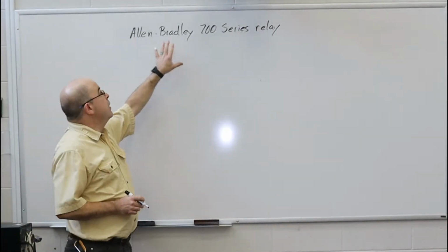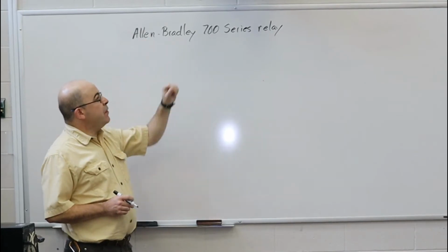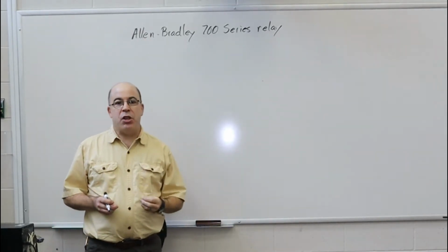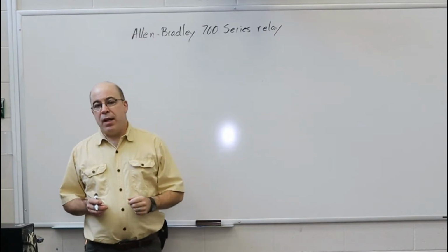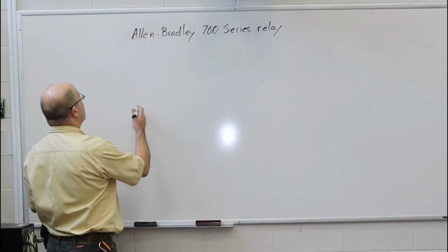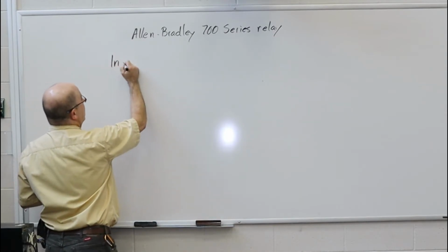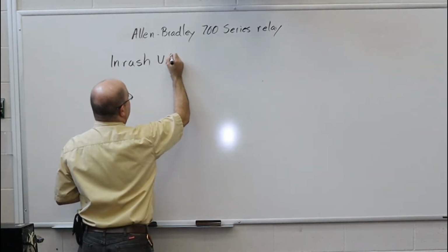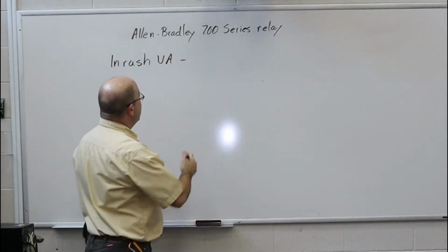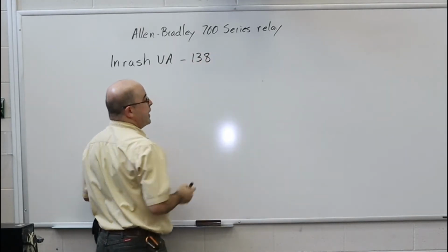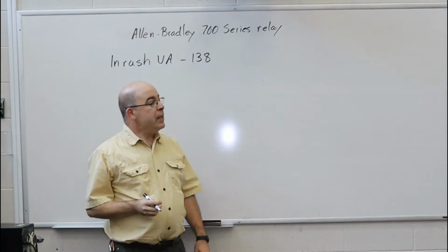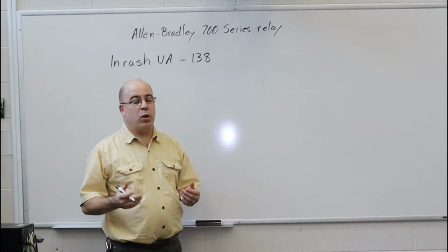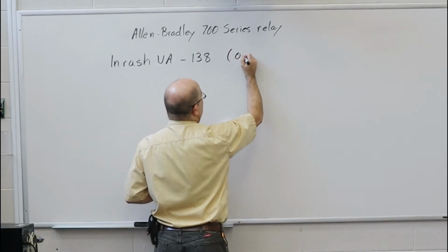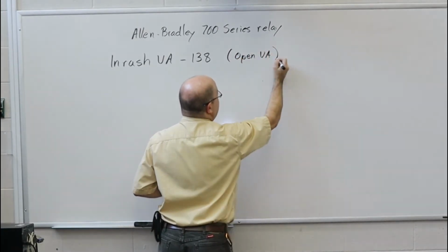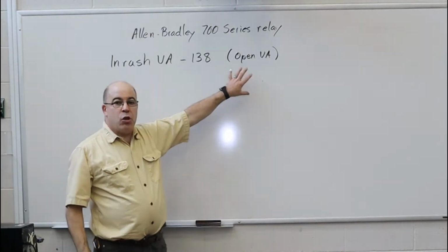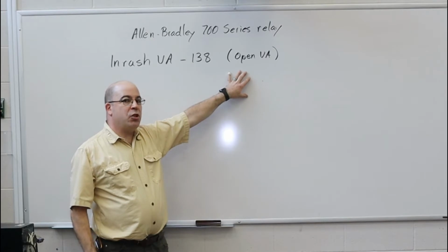Inside of these contactors, the company has used what we call Allen Bradley 700 series relay. In the specifications provided to us by the manufacturer, we got the following two pieces of information. We call the inrush VA for this particular relay 138 VA. Now, depending on the manufacturer, inrush VA could also be substituted for another term they call the open VA, meaning that your relay, the coil is at rest, the armature is in the open position.